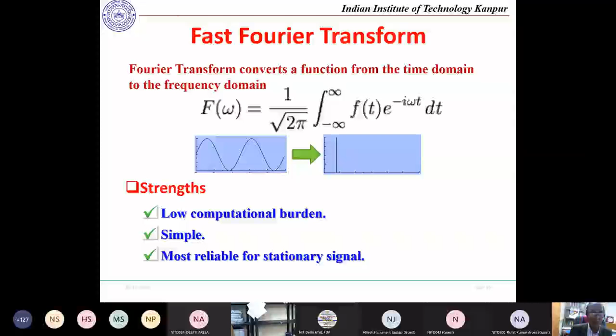But at a later stage, if the variations are very high, you cannot use even your FFT. The major problem with the fast Fourier transform is its poor resolution, which makes it difficult to detect the interharmonics. Even if the signal is there, the information you get will be wrong. Even using DFT, if I don't want interharmonics and only want harmonics, it will still not give the correct harmonic information.